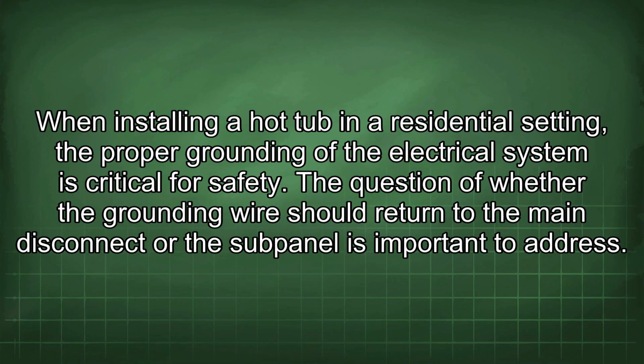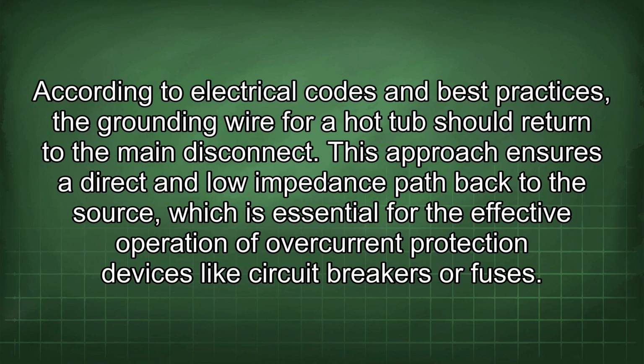When installing a hot tub in a residential setting, the proper grounding of the electrical system is critical for safety. The question of whether the grounding wire should return to the main disconnect or the subpanel is important to address. According to electrical codes and best practices, the grounding wire for a hot tub should return to the main disconnect.